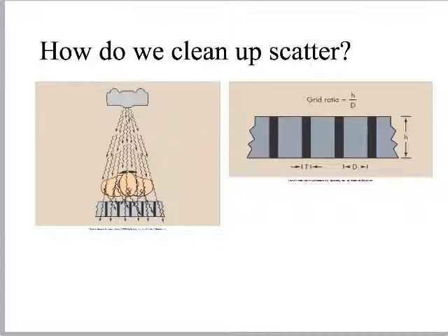So we said that Compton effect happens in all directions. In fact, it's our primary form of occupational dose, Compton effect coming off the patient. Backscatter radiation, the stuff that's being backscattered back towards the tube, I don't give a crap about because it's not going anywhere close to my image receptor. But those nasty ones that scattered inside the patient and then are going to try to interact with my image receptor, nuh-uh, I'm not playing that game. So the grid stops that cold. How does the grid do it? Well, that's what we're talking about when we talk about this grid ratio stuff over here.